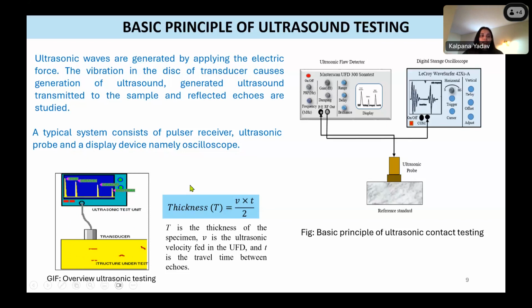So ultrasonic waves are basically generated by electrical force. The vibration in the disc of the transducer causes the generation of ultrasound, and a typical ultrasonic testing system consists of a pulser receiver, an ultrasonic probe, sometimes called a transducer, and a display device, mainly an oscilloscope. The right side of this setup is the basic principle of ultrasonic contact testing, where the ultrasonic probe makes direct contact with the reference standard. But you need to put some kind of liquid couplant. Sometimes we use oil or honey to have proper contact with the sample, so there is maximum energy transmission into the sample. Here the ultrasonic flaw detector is used for generation and reception of ultrasound, and the digital oscilloscope displays your signals.